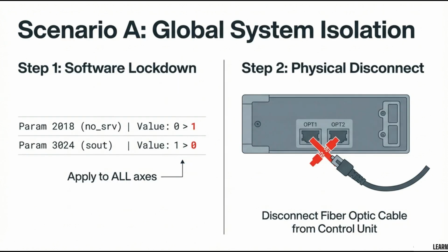Scenario A is global system isolation. Step 1 is software lockdown. Set param 2018 value from 0 to 1 and param 3024 value from 1 to 0 applied to all axes. Step 2 is physical disconnect. Remove the fiber optic cable from the control unit.